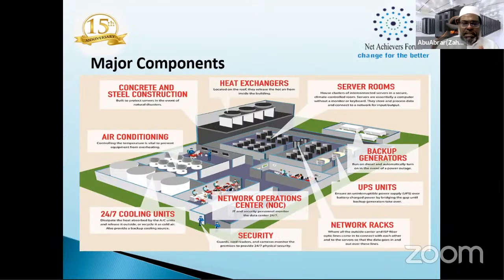Normally it has to be sealed completely. There should be no small gap. Just a few inches, centimeters, or even millimeters of gap makes a big difference in controlling the air and humidity, especially in countries like Kuwait and the Middle East. In the humidity season, a lot of issues arise everywhere because most buildings here are not designed for the data center. The building has to be designed for the data center so there will be no issues in future handling of air handling.